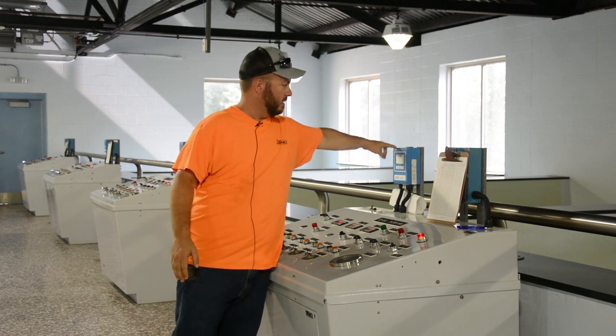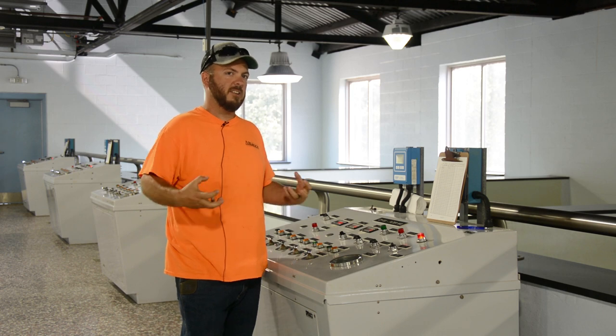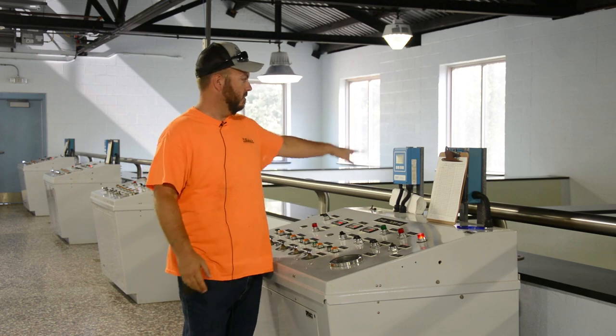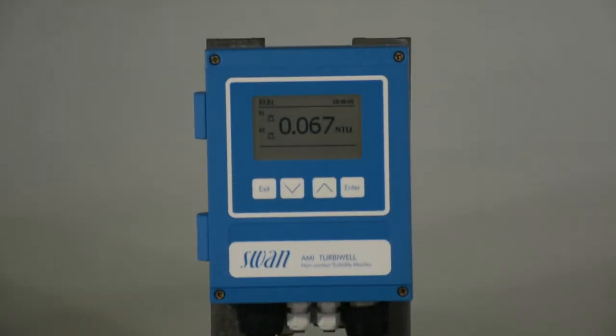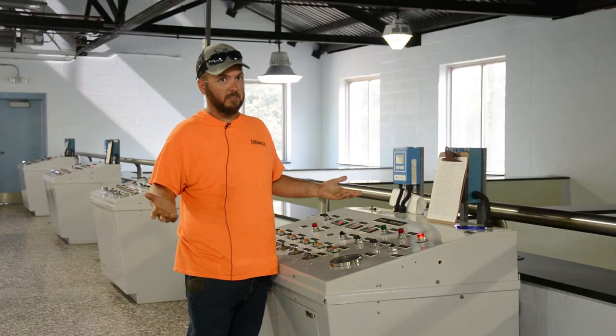The way we do that is we look at this meter right here — it's called turbidity. Turbidity is basically the cloudiness of the water. We want to keep that as low as possible; we want that water crystal clear and clean. So when this number starts getting high, we immediately wash the filter.